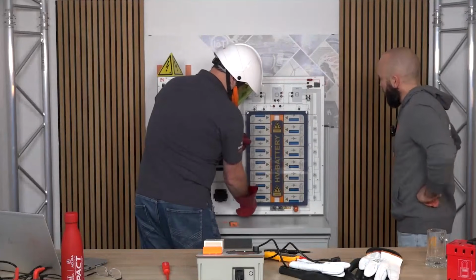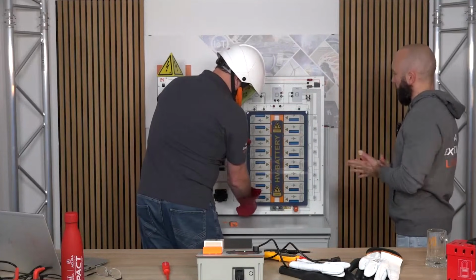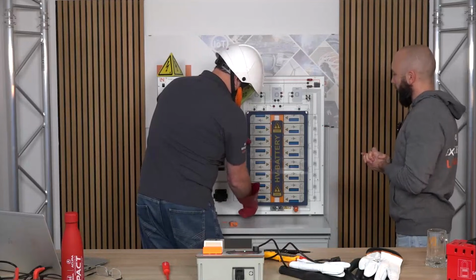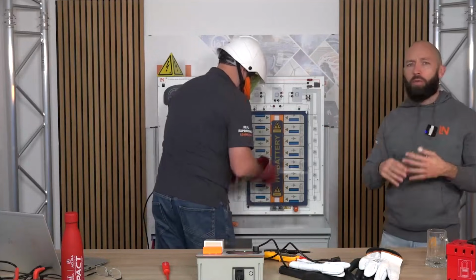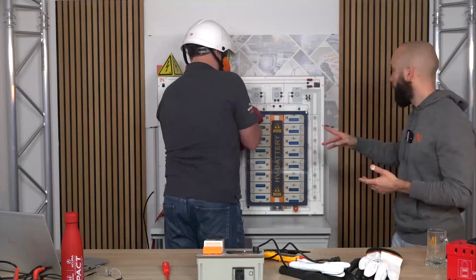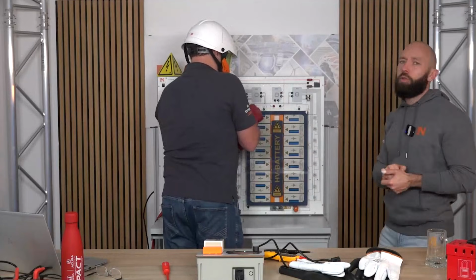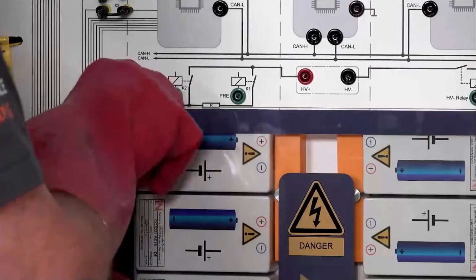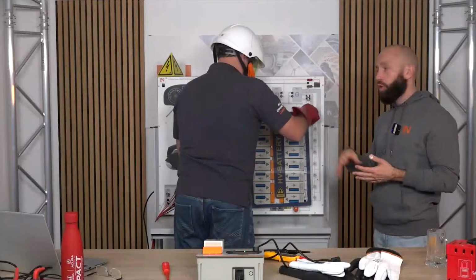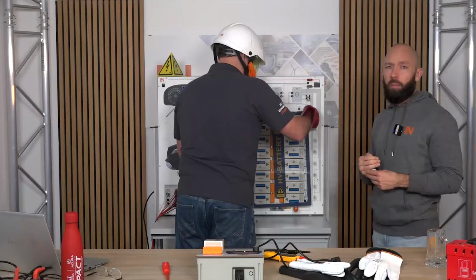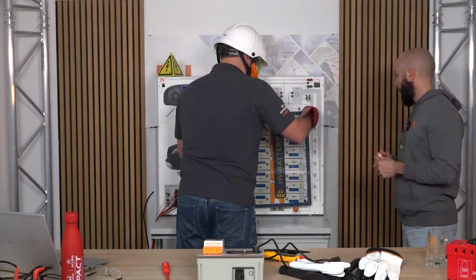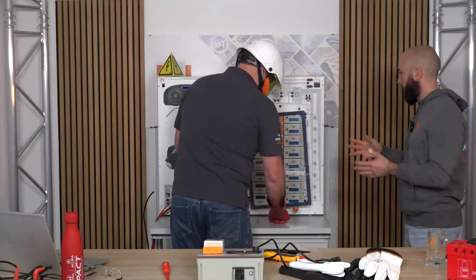Okay, in the first step now we have to disassemble the cover, right? Basically the cover is also part of the interlock. So when you open the screws, or the students open the screws while the system is not shut down, or while the system is live, this will cause an interlock fault, which you can also measure at the interlock testing points.